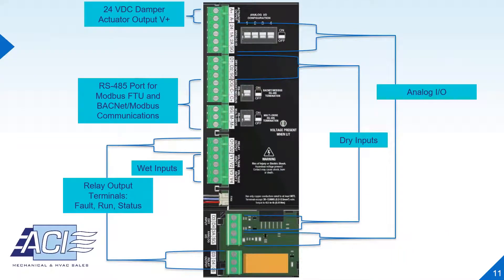This is the digital and analog control circuit terminal layout for the control board. It has a damper, so when the VFD receives a run signal, it can send power out and once the damper is open, the VFD will tell the motor to run. There are also dry and wet inputs along with configurable relay outputs, BACnet and Modbus communications, and analog inputs and outputs.